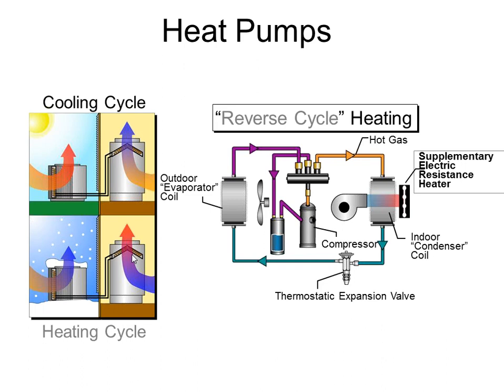We basically swap the responsibility of the evaporator and condensing coils. The condensing coil is now inside, the evaporator coil is now outside. If you look at it from a piping standpoint over here on the right, there's mainly one component that's really different from a service standpoint, and that's the reversing valve. That's this guy up here with the 3 ports on top and 1 on the bottom. His job is basically to just switch the direction of the refrigerant flow in order to swap the condenser and evaporator. Oftentimes you'll hear heat pump guys refer to them as indoor coils and outdoor coils instead of condenser and evaporator like we normally do on the air conditioning side, and that's because each coil does both jobs depending on the season.